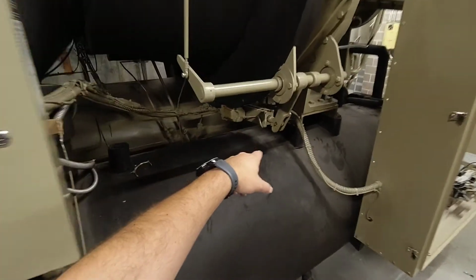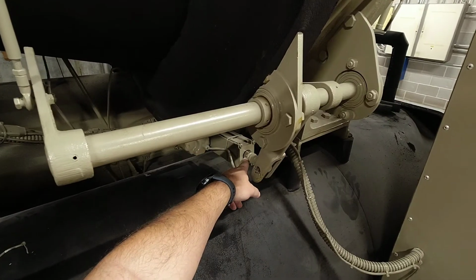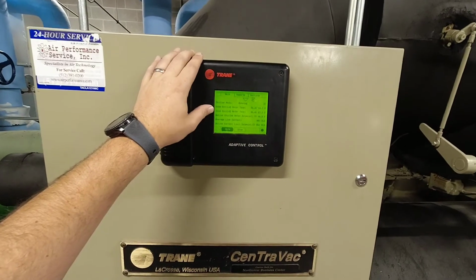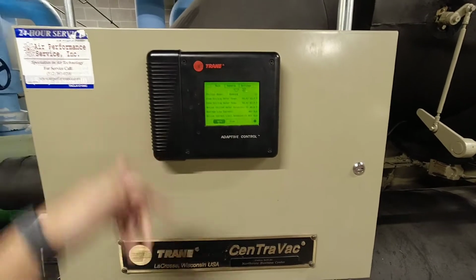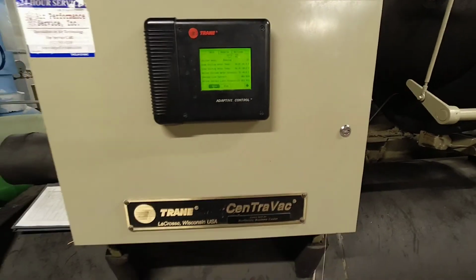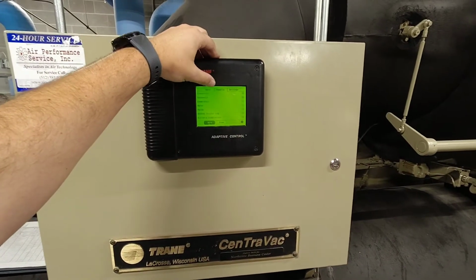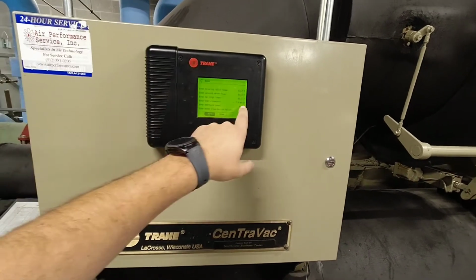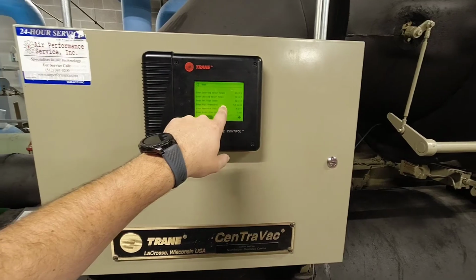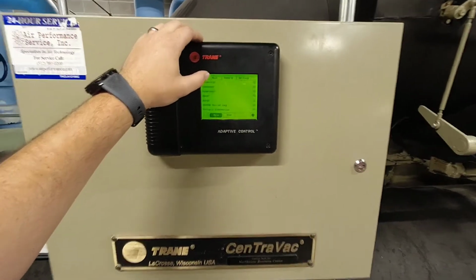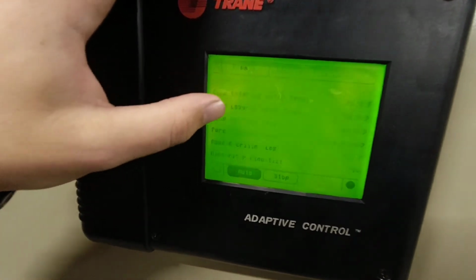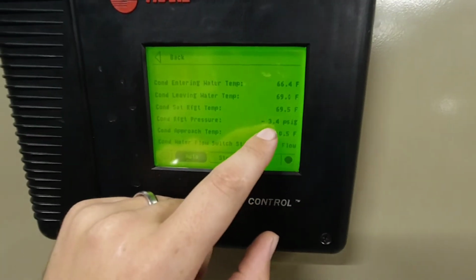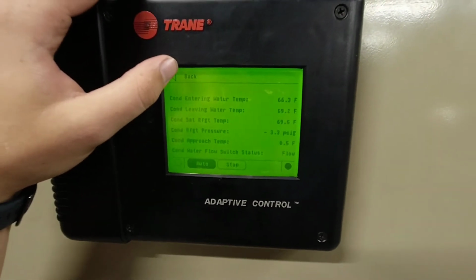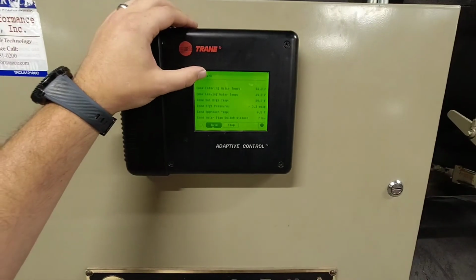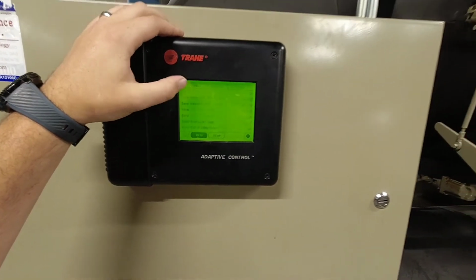You can see the guide vane here is slightly opening very slowly. Now it's going to run at a minimum load for several minutes as it goes through a startup procedure. And here's something I want to warn you guys about. This pressure right here on the evaporator, let me get in there, and on the condenser, those pressures are not actual transducer pressures.